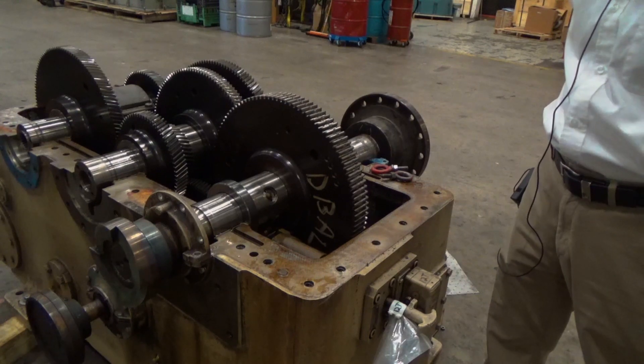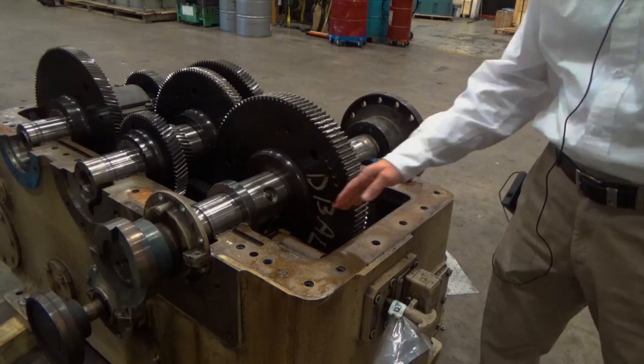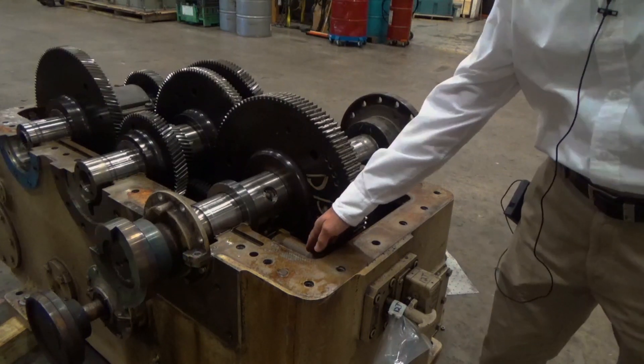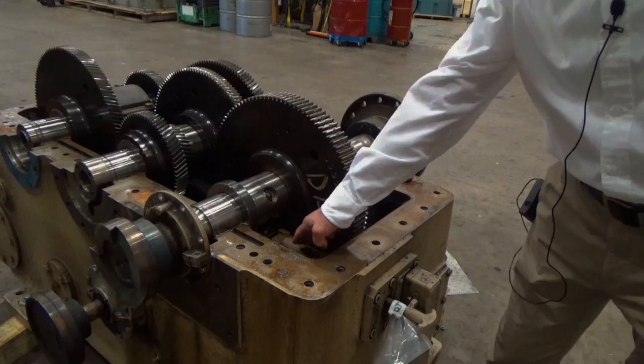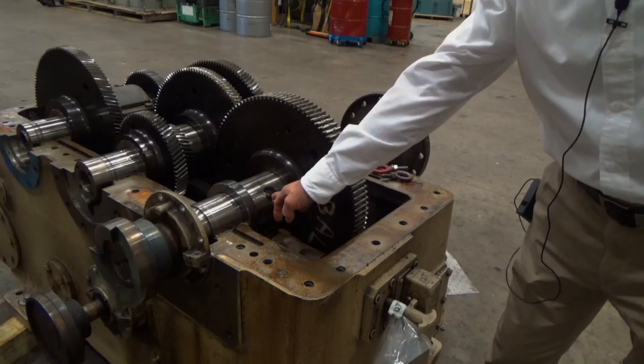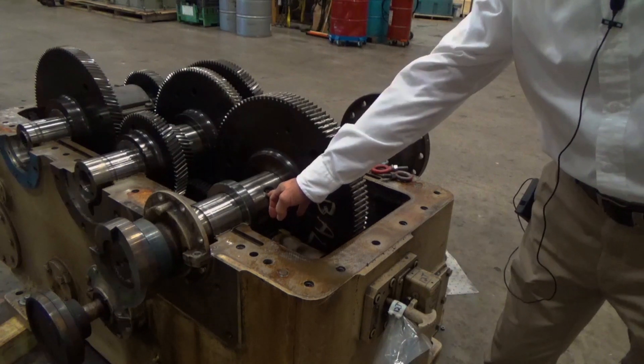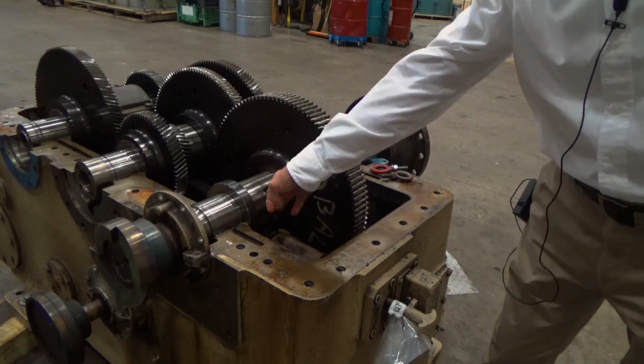This consists of internal and external components. Internally, we have the trip mechanism itself, which has an oil cavity inside. You have a plunger and a trigger. In the shaft, the rotating device is the trip bolt, which has a spring-loaded plunger.